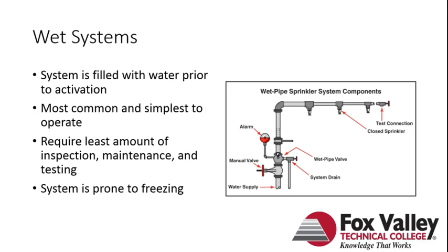I worked for a company that did a lot of sprinkler work, and in the winter, especially when we'd get a really, really cold snap, we'd start getting pipes that would freeze up because they wanted to save money. Well, we'll just put a wet system in, then all of a sudden they didn't keep that area heated the way they were supposed to.